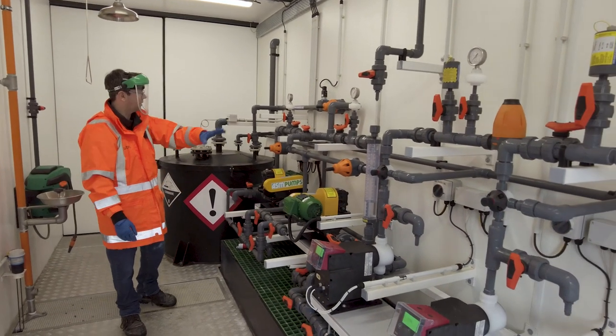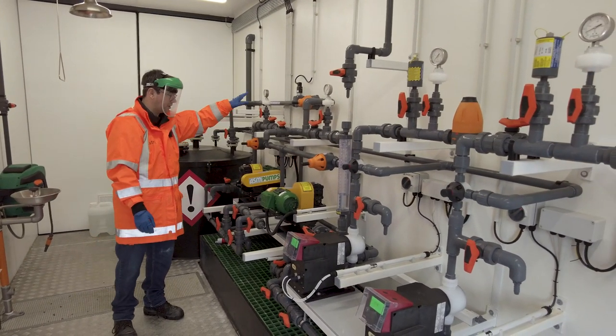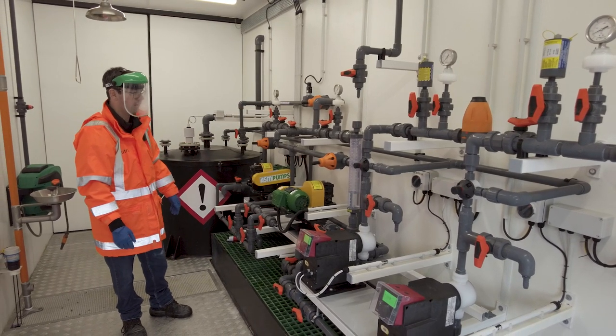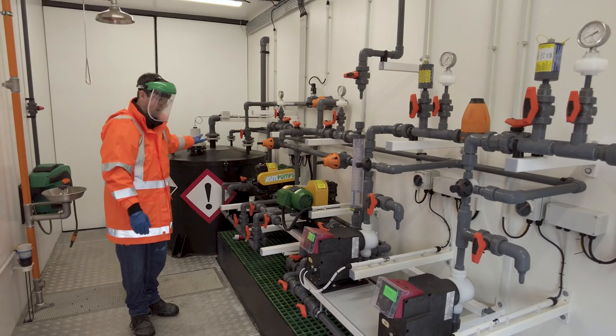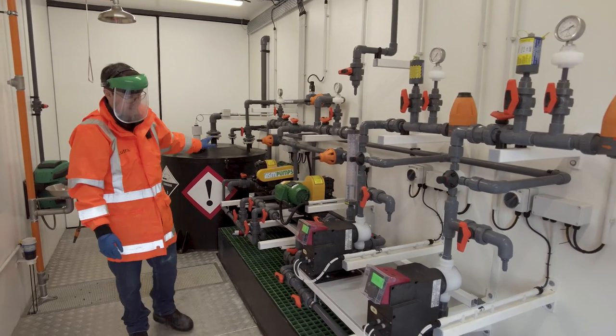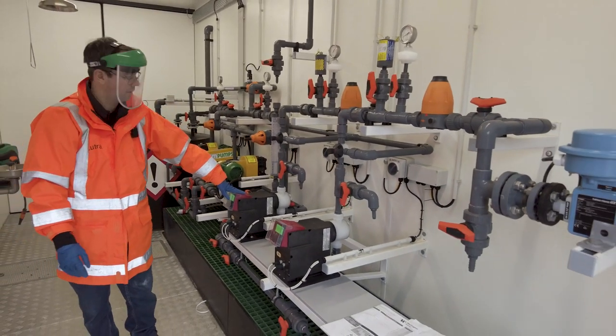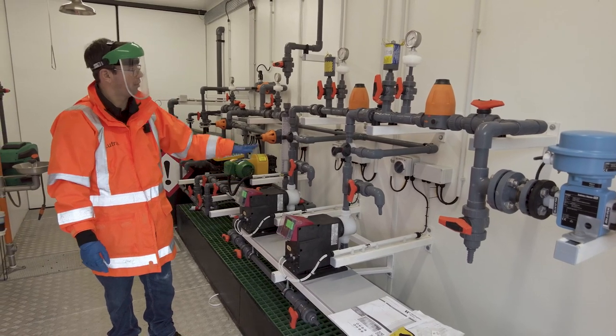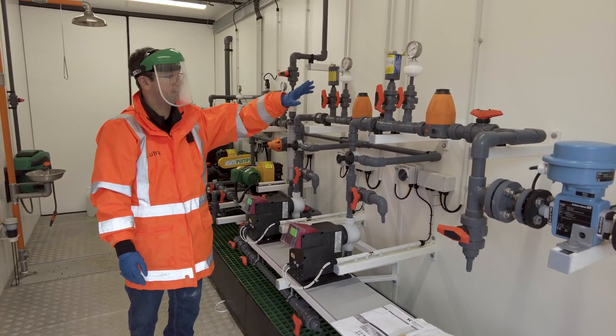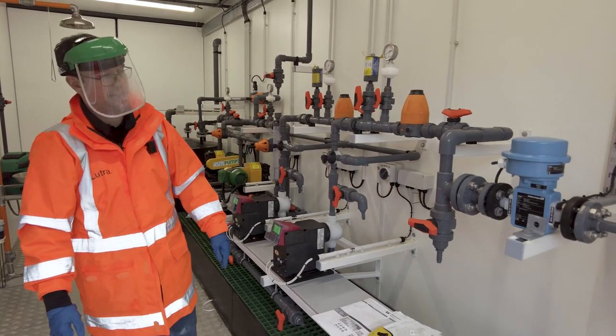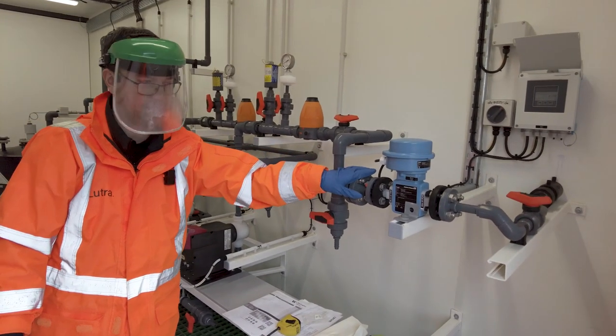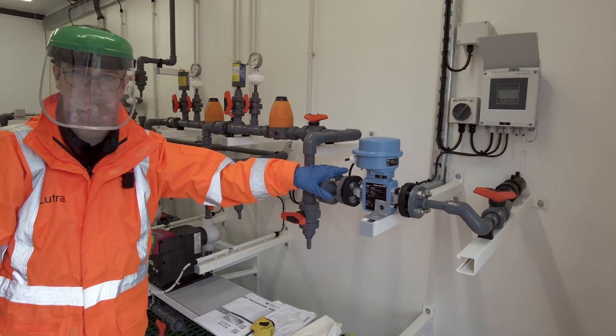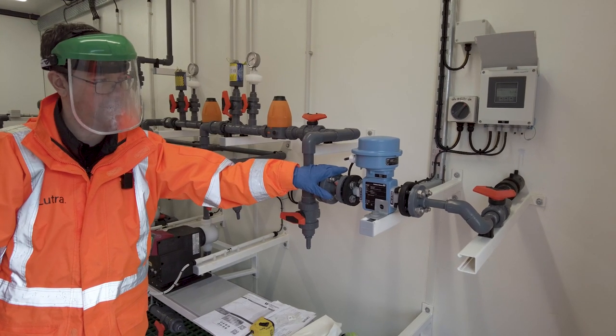On the transfer system we have a series of safety features in the event of any kind of isolated valve, and from the day tank the HFA is sucked through into these duty standby dosing pumps. These pump through a series of fittings and are then measured by a downstream flow meter. This flow meter is rated for use with HFA because it has platinum electrodes.